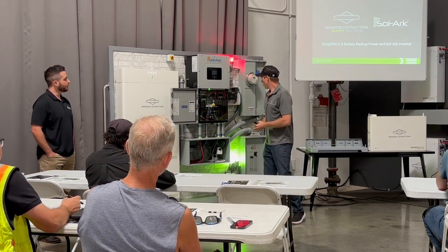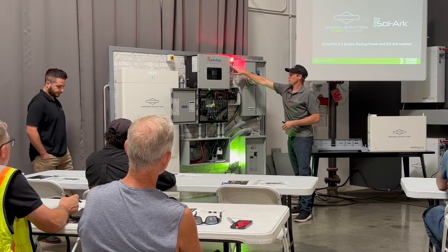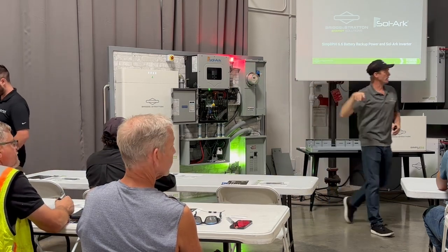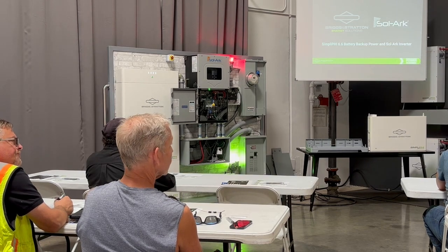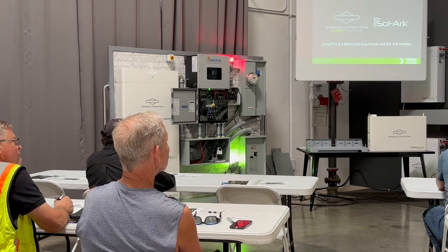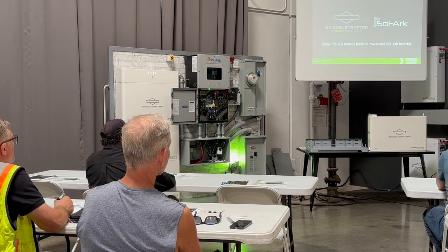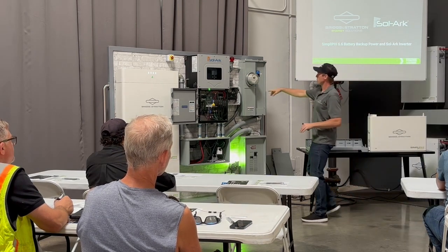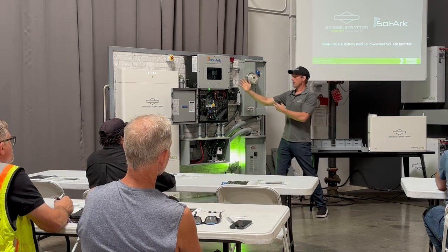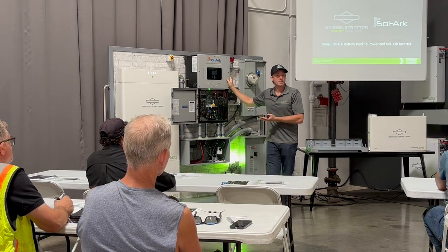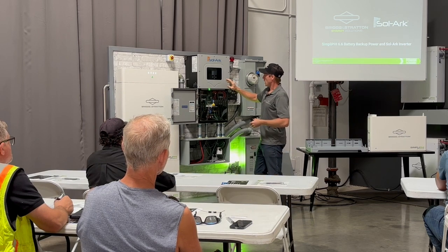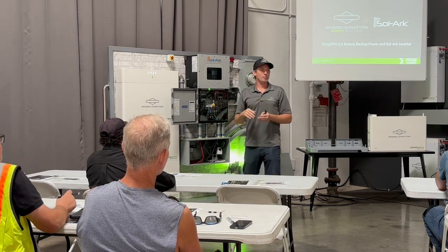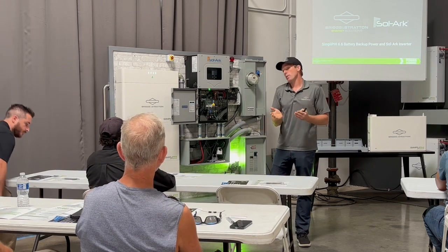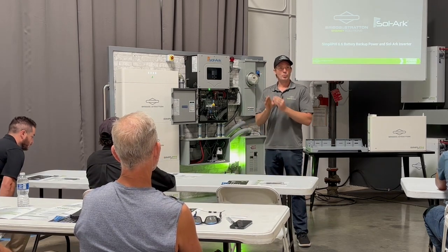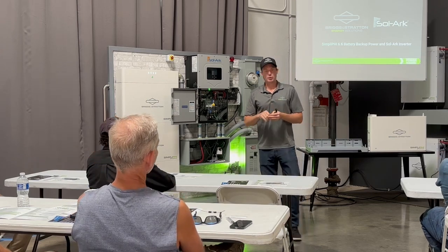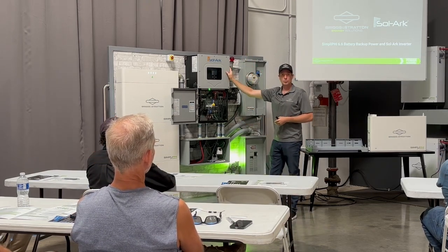Then on the AC side, what I've got right now, this red bulb that's up here indicates the grid. So John has wired 240 split phase for me. And so when I pull this, it's like a grid going out, and you can see the red light here on the display wall go out. So there's no grid coming in. You can see the meter is dead. The Sol-Ark acts as your interrupt, right? And so your micro disconnect occurs inside the Sol-Ark. It's a little bit different than transfer switches. You may know that, but what's happening inside there is really relays that are reacting very quickly. So there's 200 amp pass through from the grid through the Sol-Ark.